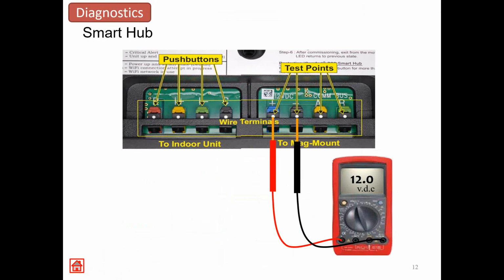And you would test it with a standard meter. Just make sure that you're on DC. Most of the meters this day and time will auto select, but just in case, I always like to make sure they understand that we're talking about DC voltage. And a lot of this stuff, once we get high voltage converted, we're at DC voltage. Our outdoor fan motor operates that way, the compressor operates that way, and also our communication from our Smart Hub to our display operates that way.